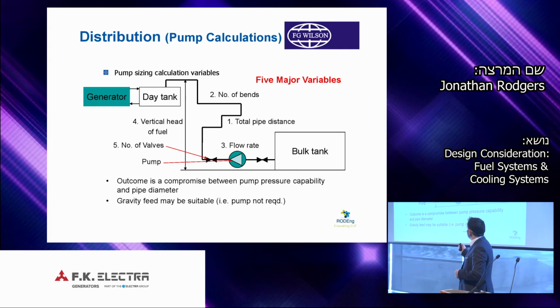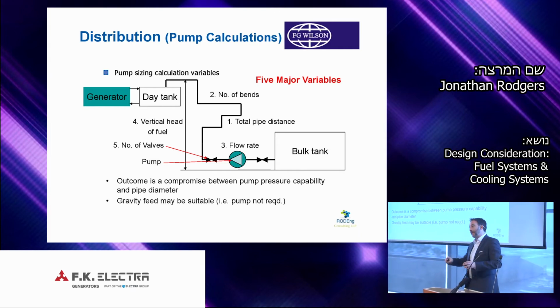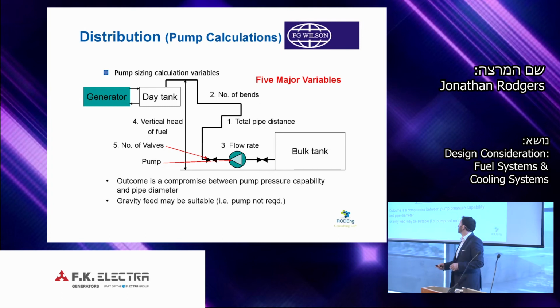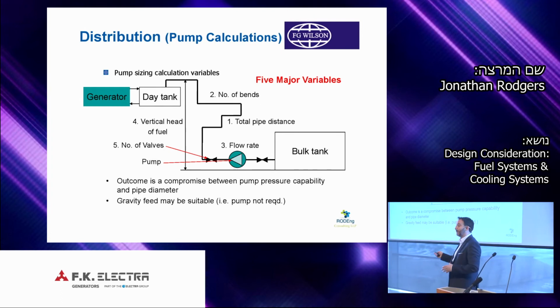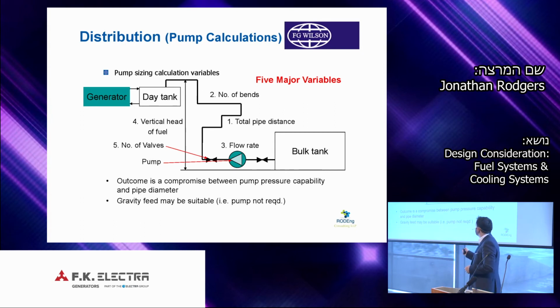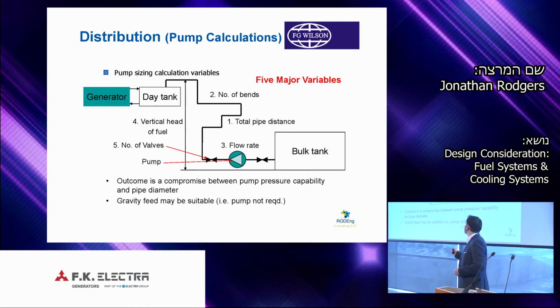So when we're looking at how to make all of these components work, we need to design the calculation for the sizing of that pump and the pipework. And these are the items we need to know. We need to know the distance of the pipe, the number of bends in the pipe, how much flow, the rate that we need to transfer flow from the bulk to day tank.